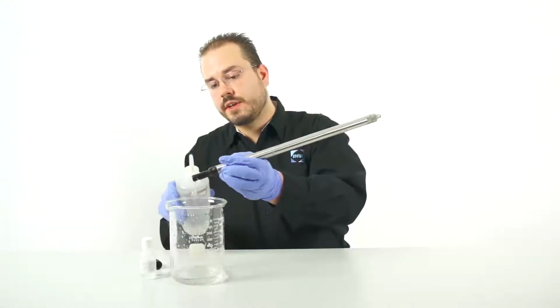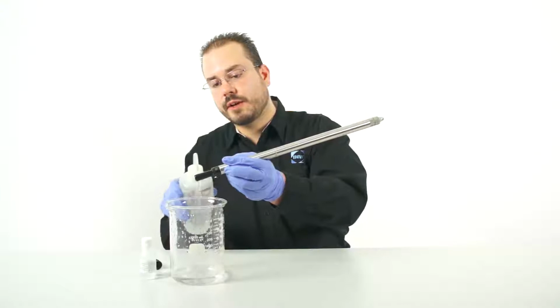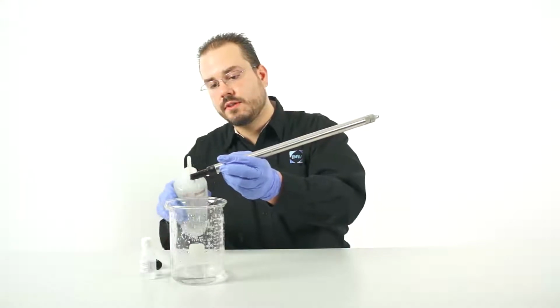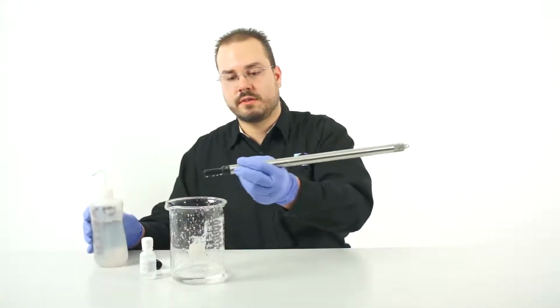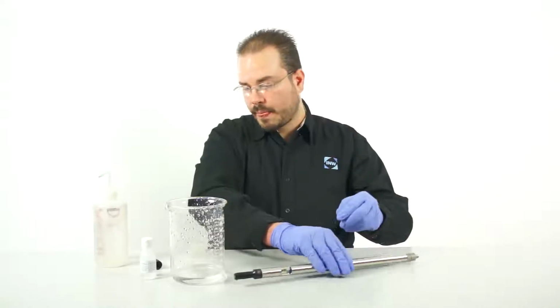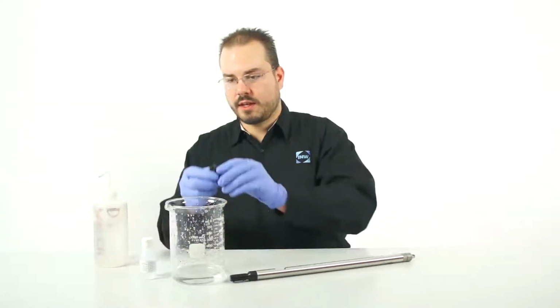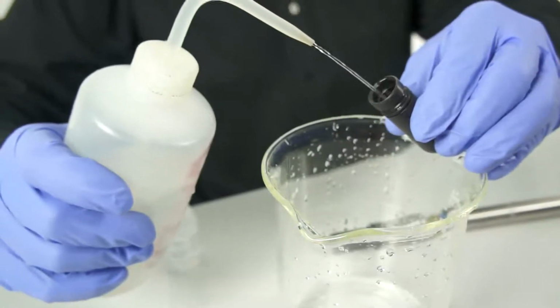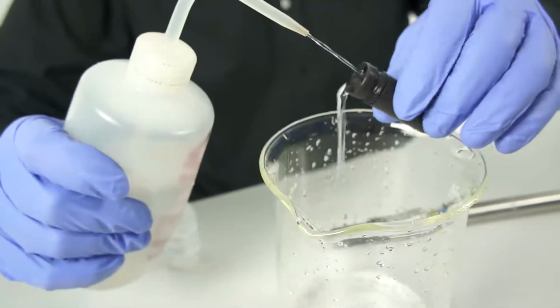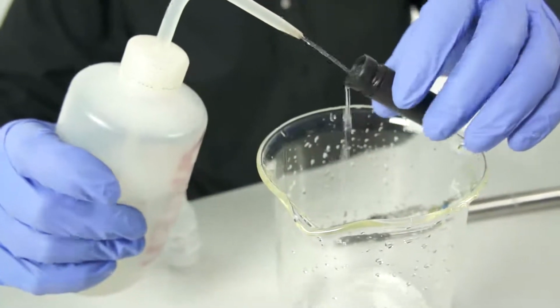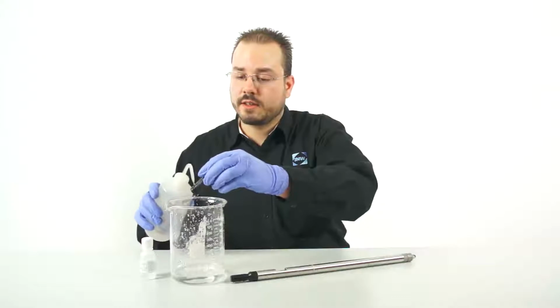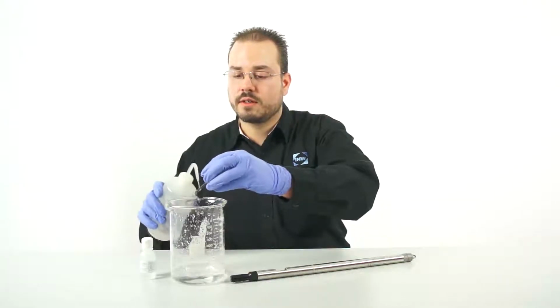I want to rinse the threads of the capillary with DI water to remove the old solution, as well as flush out the reference cap. And this will remove the old reference electrolyte along with any contaminated water.